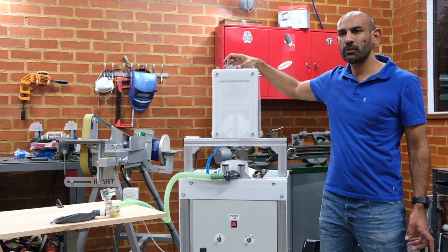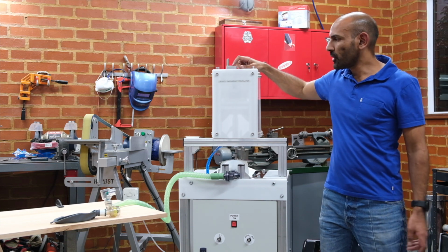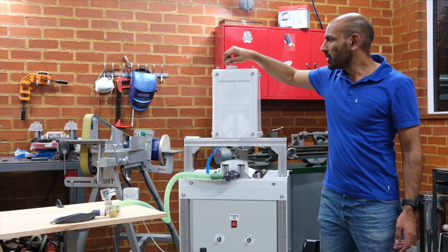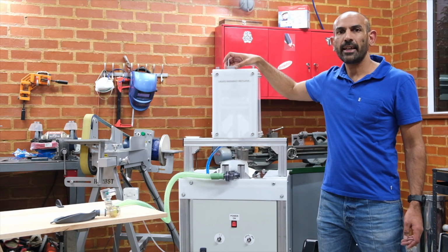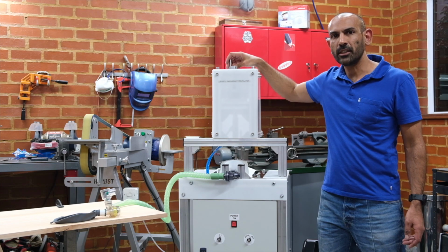Another change to this design was a problem I had with the old design that I hadn't yet sorted out: how do we control tidal volume? So I've incorporated this hand wheel, which controls the stroke of the cylinder. You can move it clockwise to increase the tidal volume, or anti-clockwise to decrease the volume.